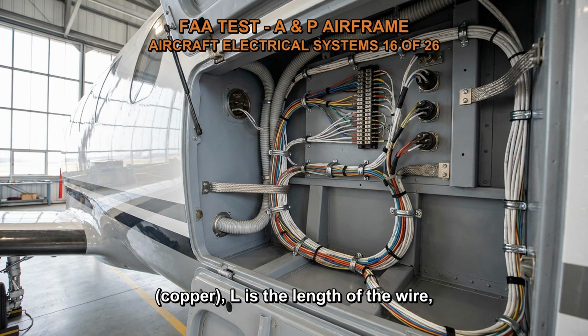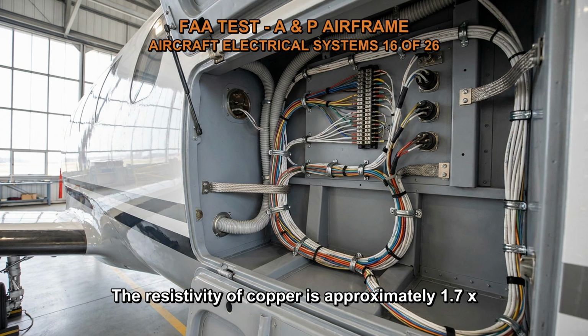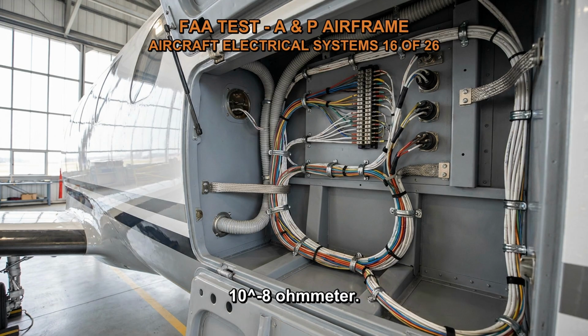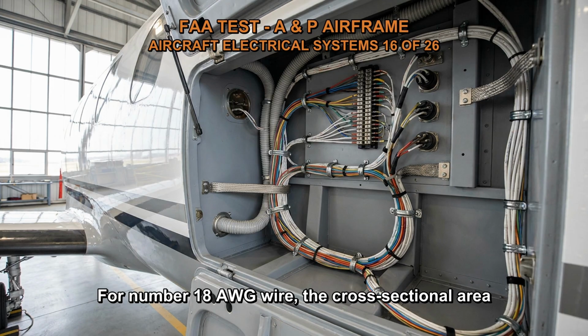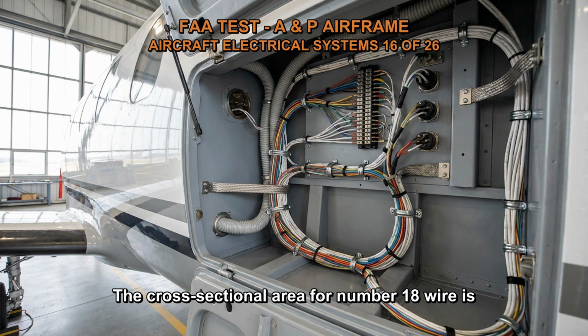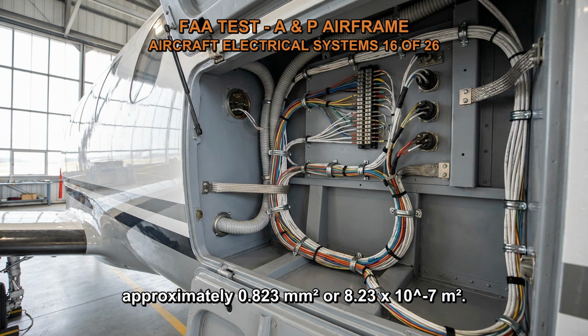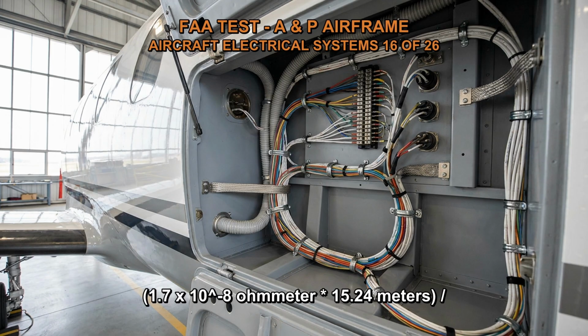The resistivity of copper is approximately 1.7 × 10^-8 ohm-meters. For number 18 AWG wire, the cross-sectional area can be obtained from standard wire tables. The cross-sectional area for number 18 wire is approximately 0.823 mm², or 8.23 × 10^-7 m². Now we can calculate the resistance. R = 1.7 × 10^-8 ohm-meters × 15.24 meters / 8.23 × 10^-7 m², R = 0.313 ohms.